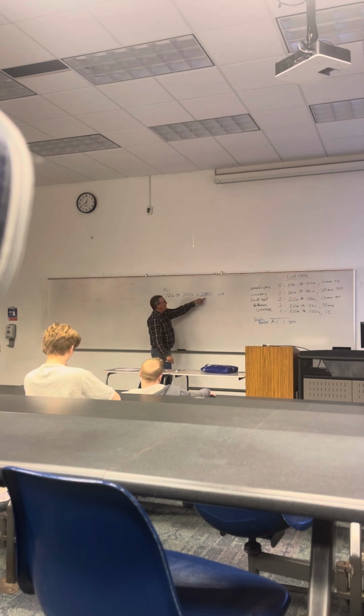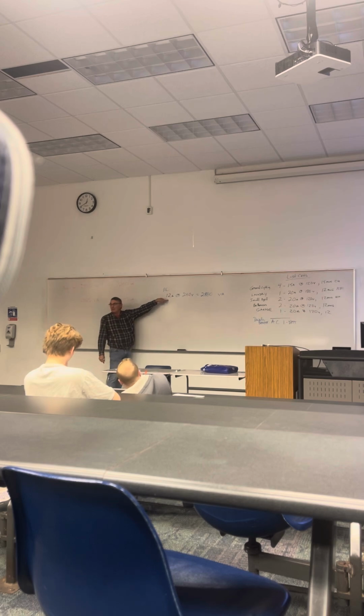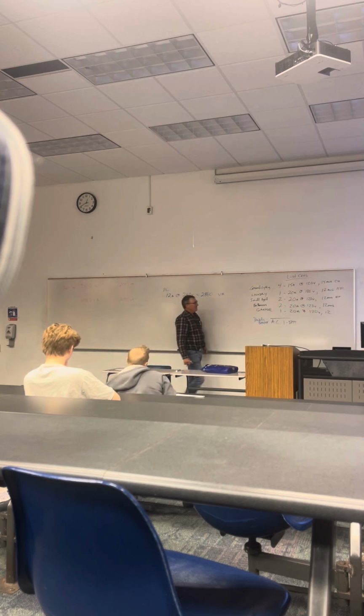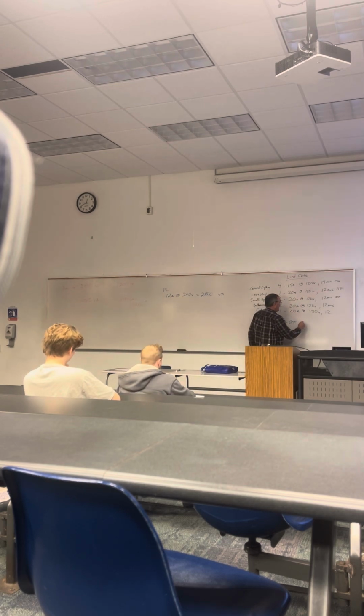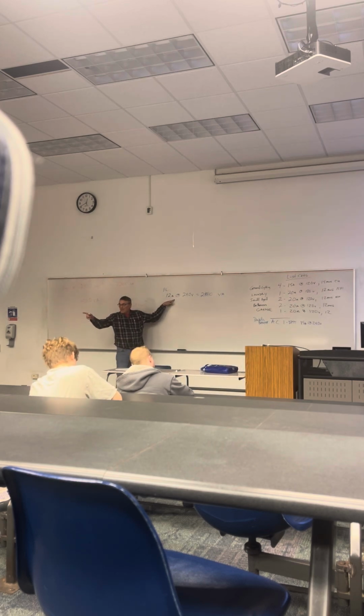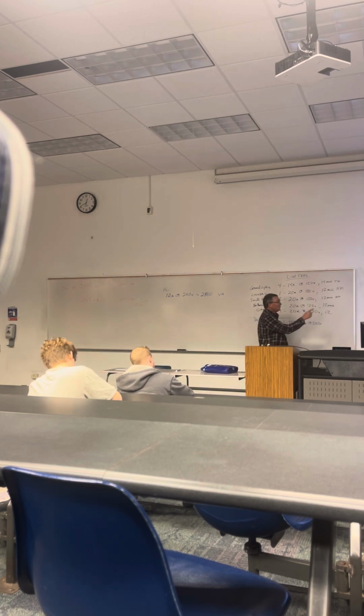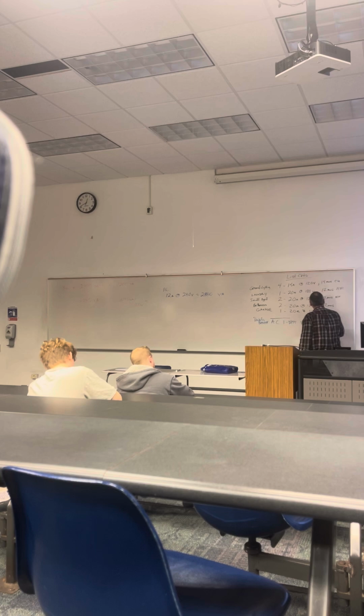How many amps for this thing? Well, they don't make a 12 amp breaker. 15 would work, right? So that's 15 amps at 240. In these units, they also have a 120 volt line. So for a strict 240, this would be 14 AWG.